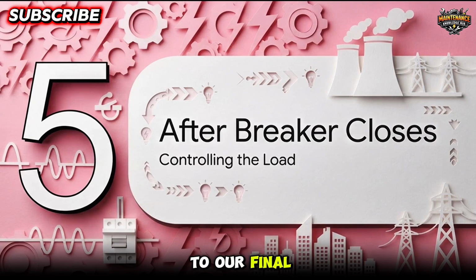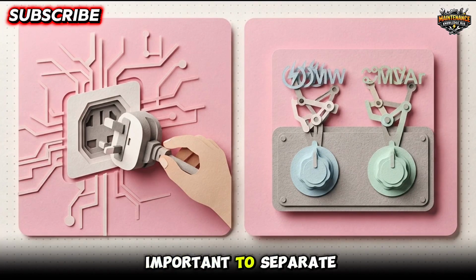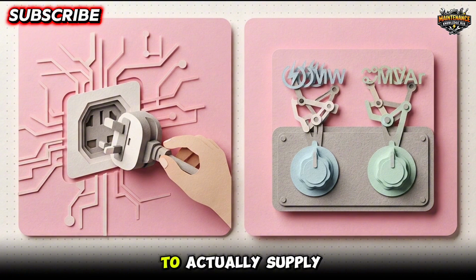Which brings us to our final section, after the breaker closes. Now, it's incredibly important to separate these two concepts in your head. Synchronization is literally just the act of getting connected safely, but right after that breaker closes, the generator is basically just spinning along holding hands with the grid, but not actually doing any of the heavy lifting. To actually supply power, we have to enter a new phase called load sharing. And that's where we control exactly how much active and reactive power the generator pushes out after it's connected.